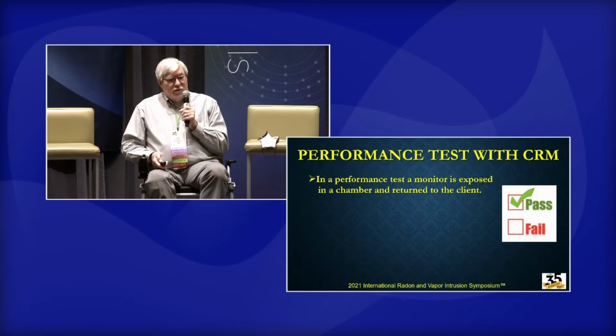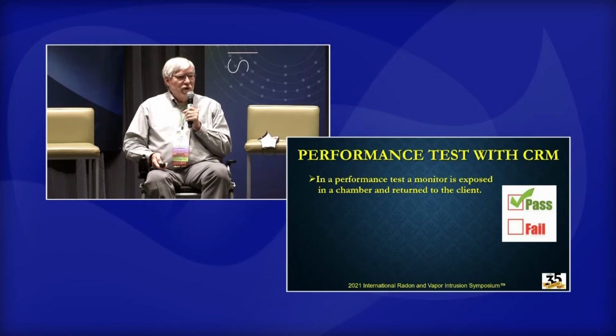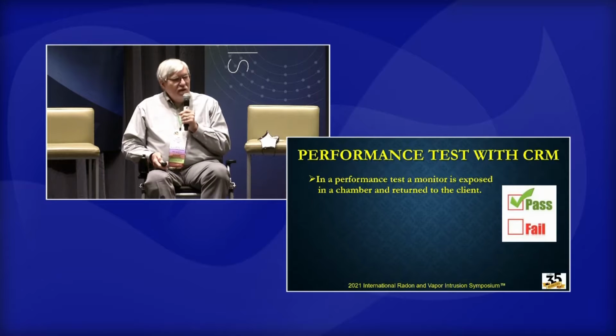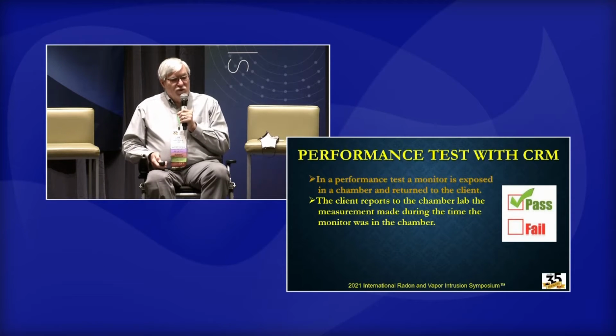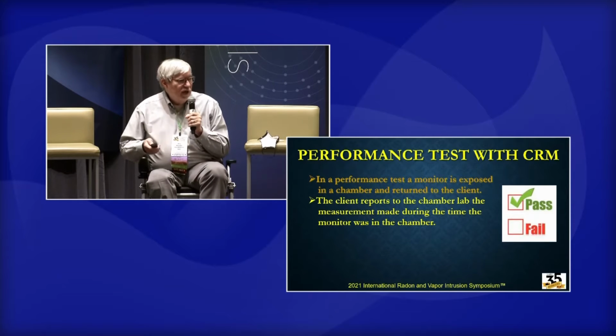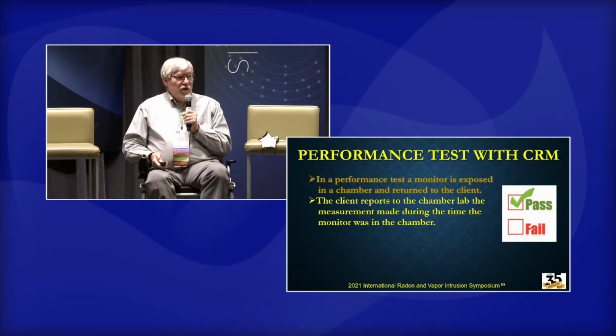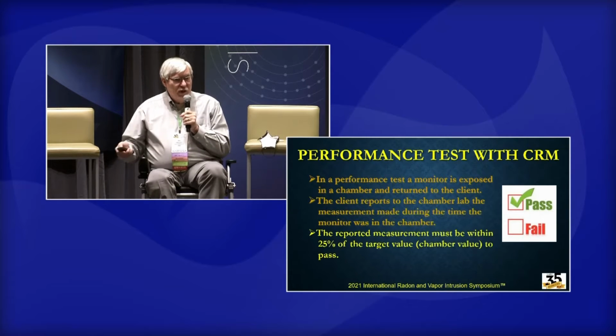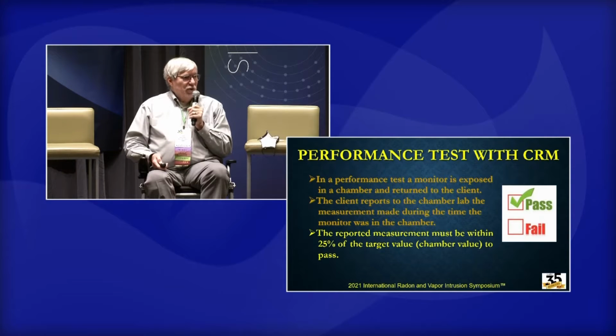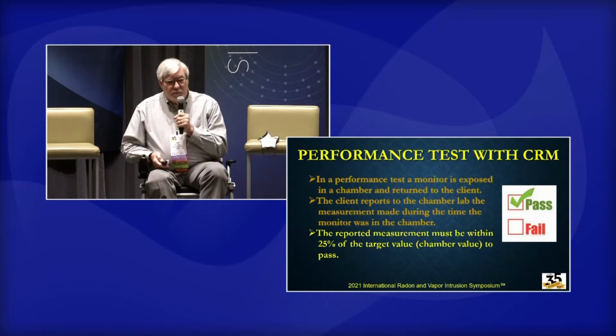So I'll talk a little bit about performance testing with a continuous radon monitor. The client sends a monitor in, we expose it in a chamber to a known concentration, and then send it back to the client. The client reports back to the chamber lab the measurement that was made during the time the monitor was actually in the chamber, in other words, to agree with the chamber average. And the reported measurement must be within 25% of the target value or the chamber value to pass. And that usually with monitors is no real big problem.